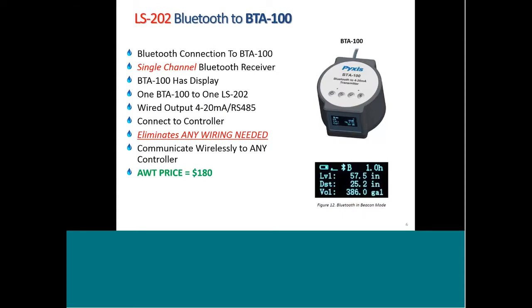We talked a little bit earlier about those customers that really aren't into using the app, but really want to use this as a conventional ultrasonic level detector in a wireless format and connect it to their existing controller. What do they do? In that case, they would want to purchase the BTA-100. The BTA-100 is a localized receiver and display. It's a single channel, so for each level indicator, you get one BTA-100. It's a very low-cost solution to integrating one tank at a time.